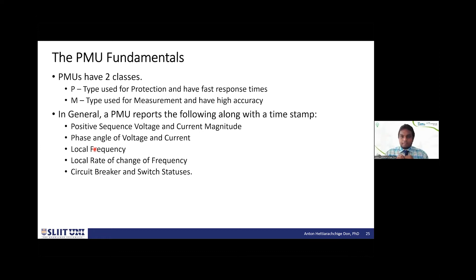PMUs report a bunch of information. The main things are positive sequence voltage and current magnitude, the phase angle of the voltage and current, the local frequency, and the rate of change of frequency within its sampling time. Utilities can configure them to also transmit things like circuit breaker information and switching states, but the main things are voltage, current, and frequency, with voltage and current given as phasors, meaning magnitude and angle.